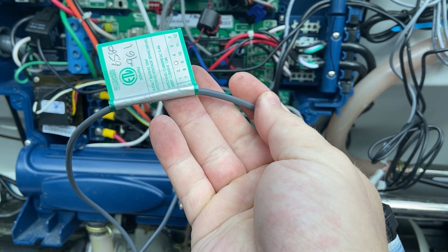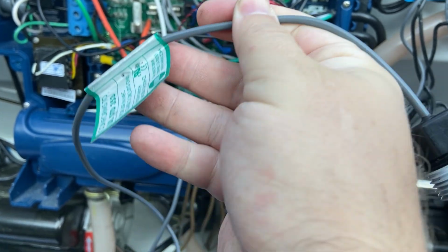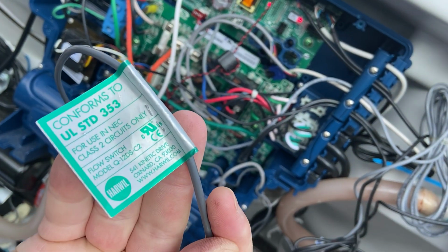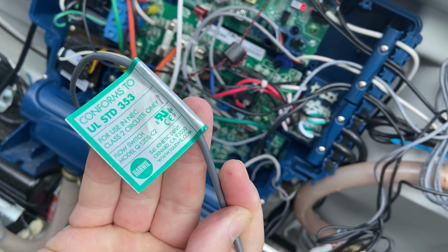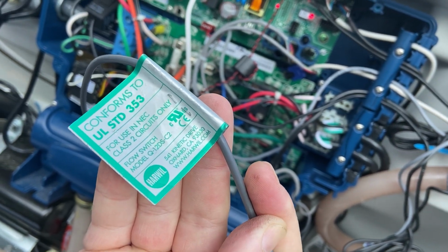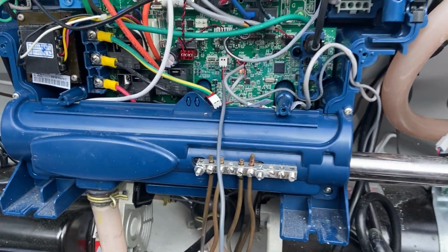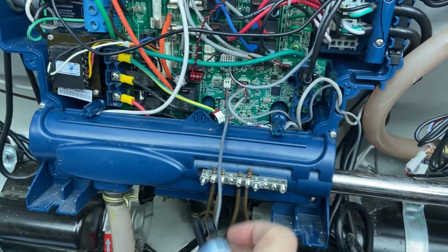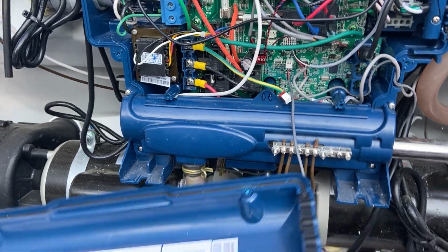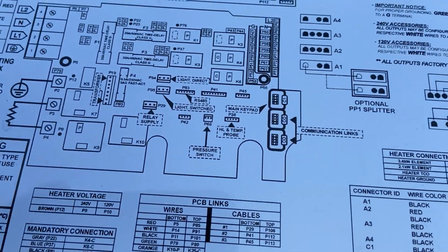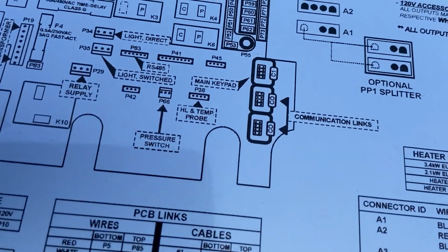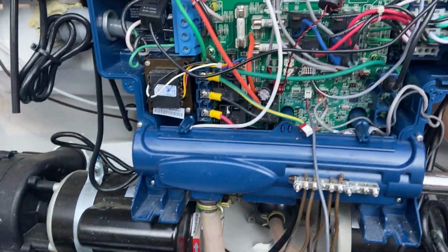You will see also the manufacturer of it. So you might look here and see a part number that's relevant to the manufacturer of the flow switch. You can sometimes find that elsewhere. That's that Q number right there. So in this case, I have a kind of test flow switch plugged in. If we wanted to know where it went, we could look at the schematic. It says pressure switch. See right there at the P66, it's referencing the flow switch.